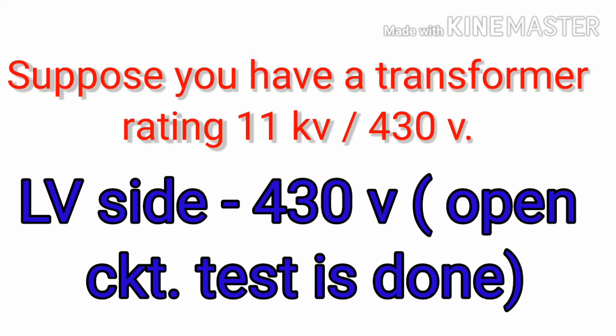Suppose you have a distribution transformer which has a rating of 11 kilovolt to 430 volt. Now 11 kilovolt is my high voltage side and 430 volt is my low voltage side. If we want to make an open circuit test, then we choose 430 volt, which is my secondary winding in this case. So we install all the instruments like wattmeter, voltmeter, ammeter in the secondary winding of the transformer, and we keep the 11 kilovolt side, which is my primary winding, open circuit. Thus we can measure the iron loss, which will be the wattmeter reading. The wattmeter reading shows the iron loss.